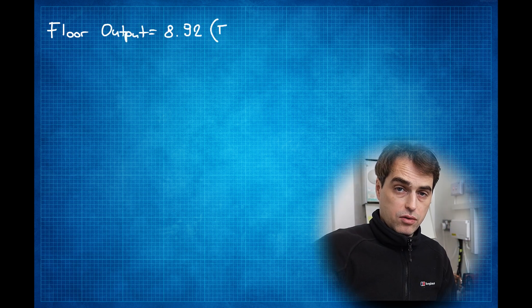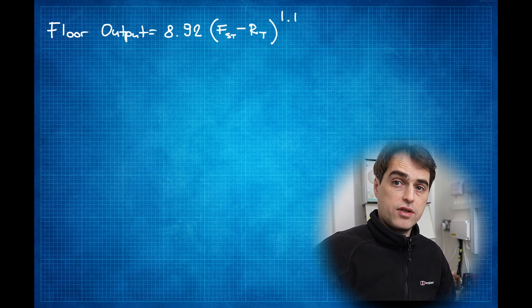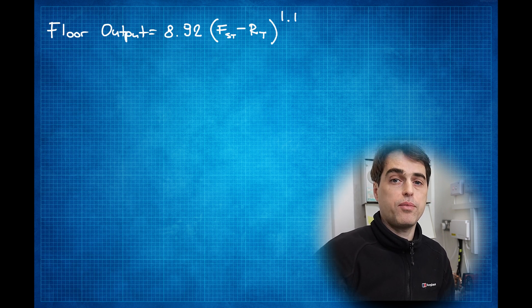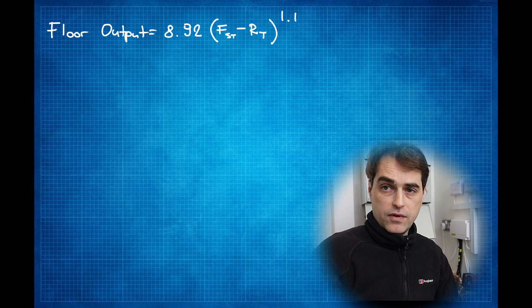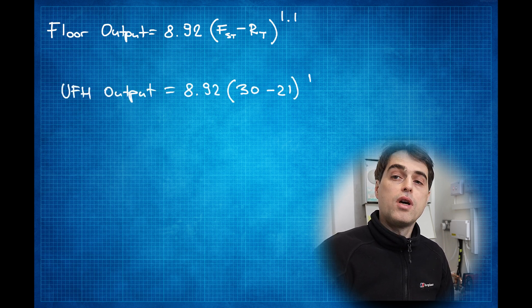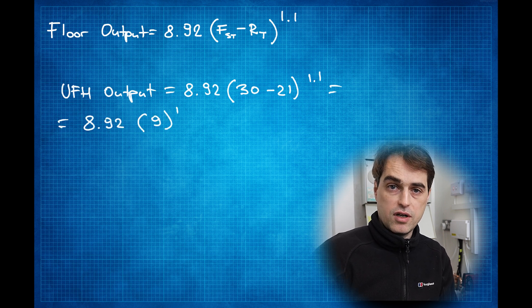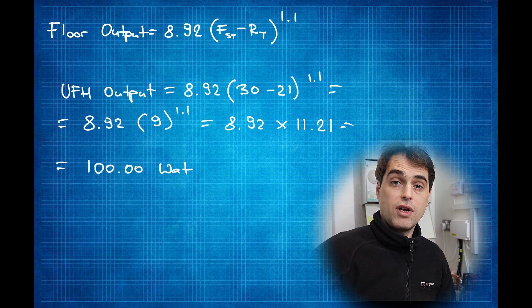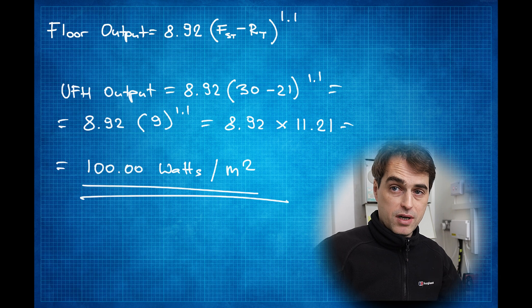If you want to know how to calculate floor output, there's an equation: floor output equals 8.92 multiplied by the difference of floor surface temperature minus room temperature, to the power of 1.1. For example, 8.92 multiplied by 30 degrees surface temperature minus 21 degrees room temperature gives 9 to the power of 1.1, which comes out at roughly 100 watts per square meter.